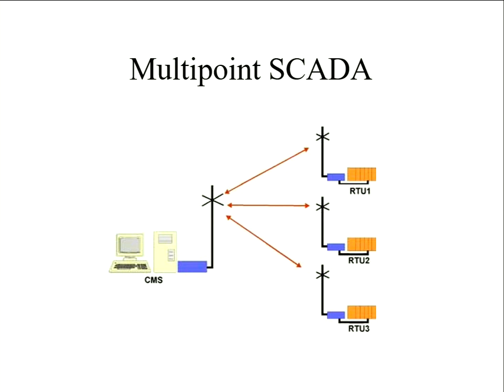You can't do that with all the stations though, because the systems aren't designed as high bandwidth systems. So it's like a poll, so the central system is the master and the outstation system is the slave. It's relatively simple. You ask for data, wait for the reply, then you go on to the next one, so you don't get data coming in from multiple sources. If it was the outstation trying to shout to the centre, you get confusion, and hopefully you detect when you don't get a reply. Usually you put in 1 or 2 retries in there, because you don't want to be, in a sense, swamping operators with alarms just to say that you didn't get a reply that time.